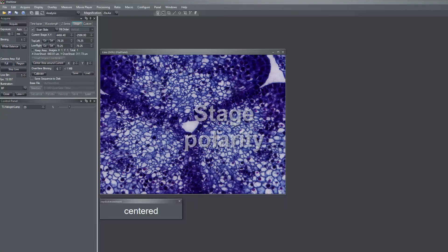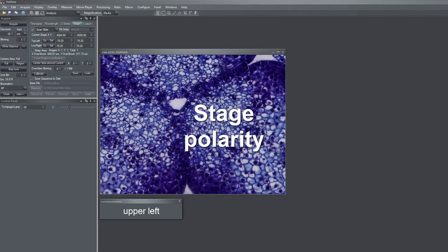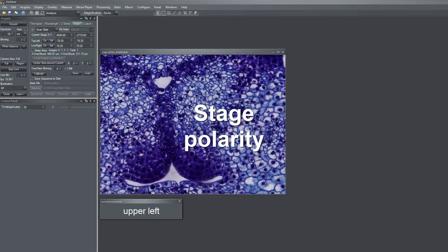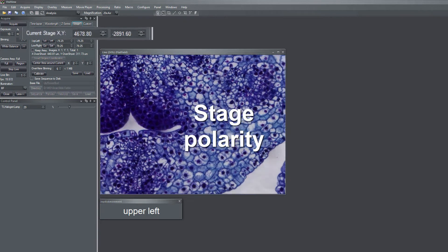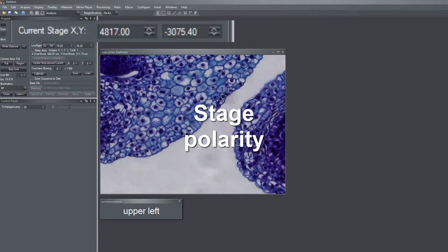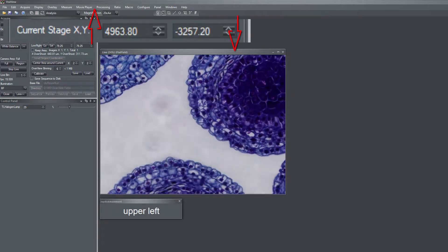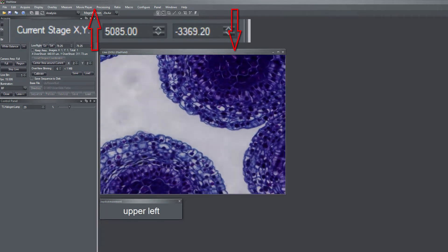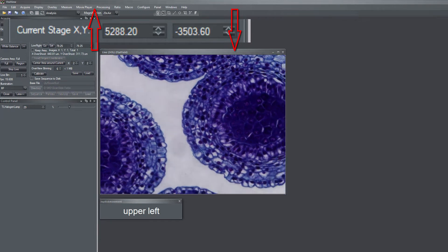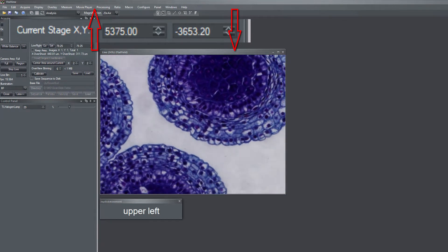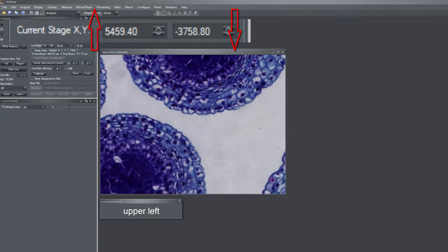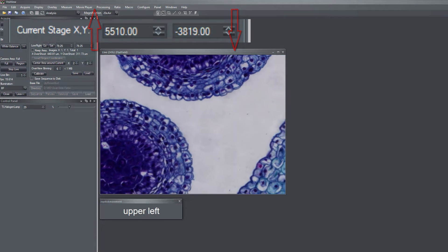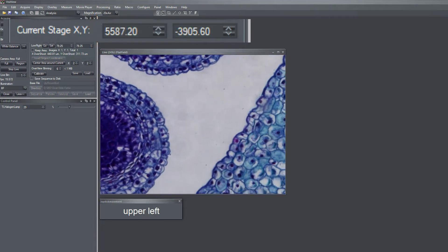The third thing you have to check is the stage polarity. If you move your sample to the upper left in the sample mode, your x and your y-axis values both have to increase. In this case, only the x-axis value increases while the y-axis value drops. So how can we fix this?